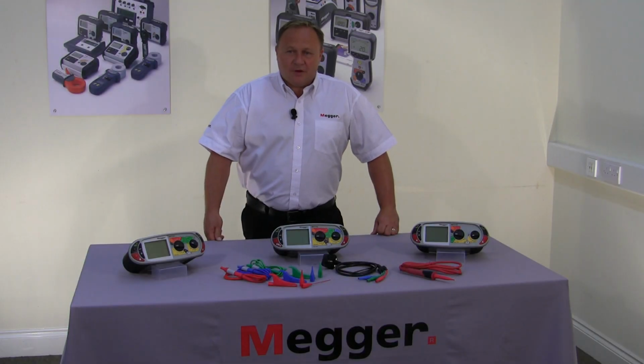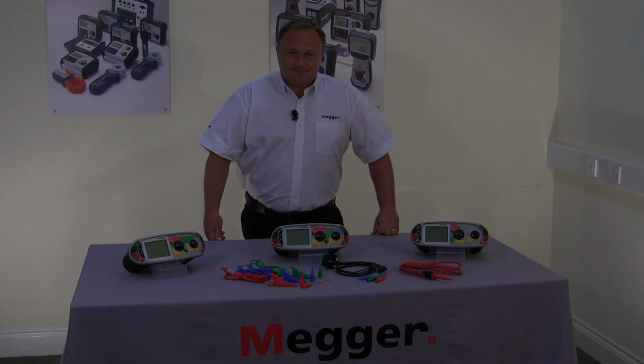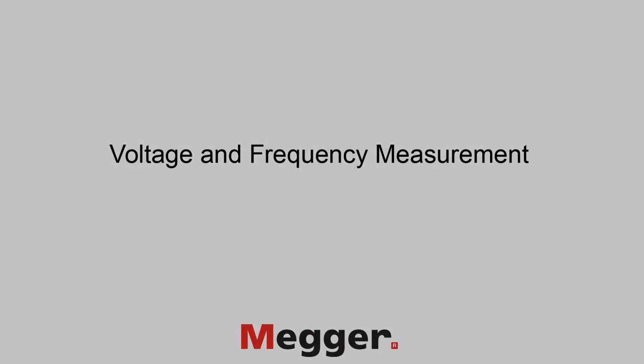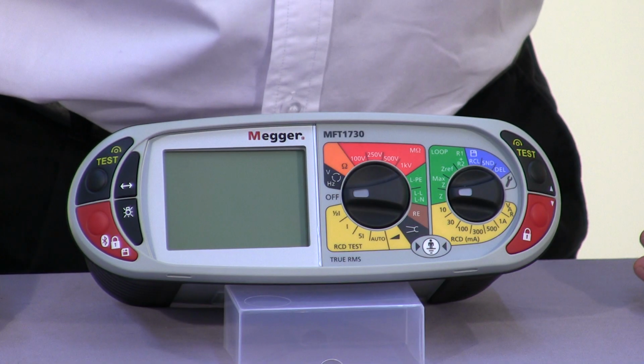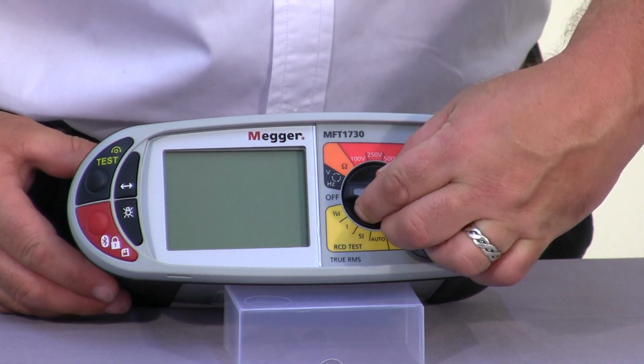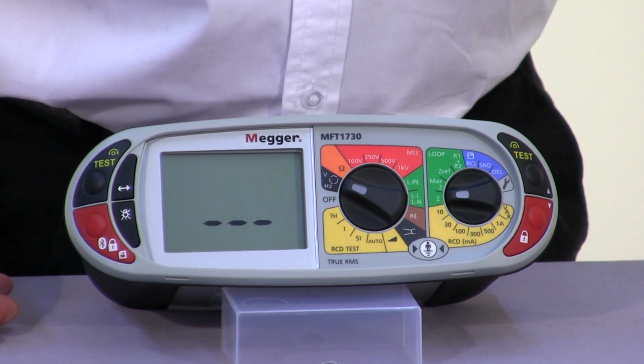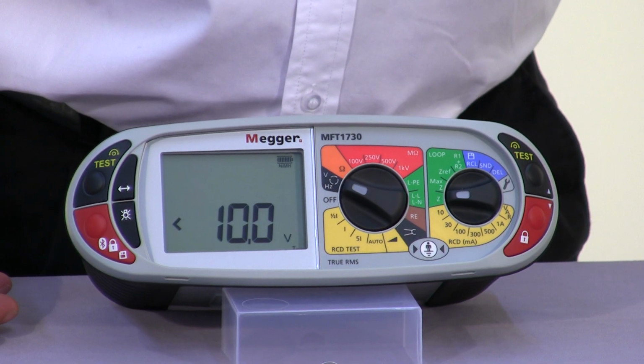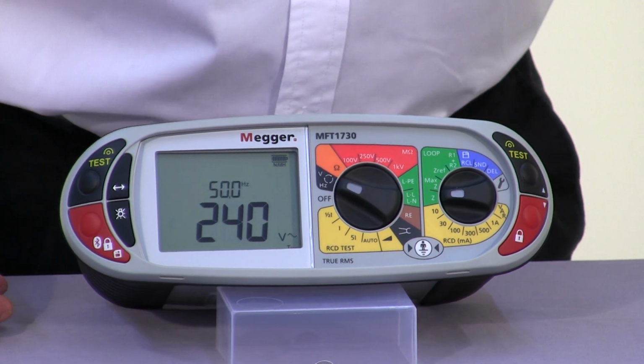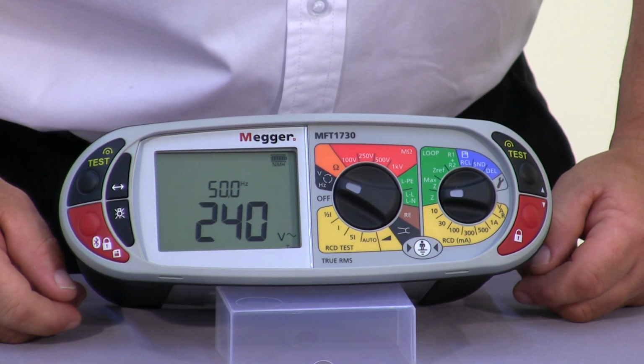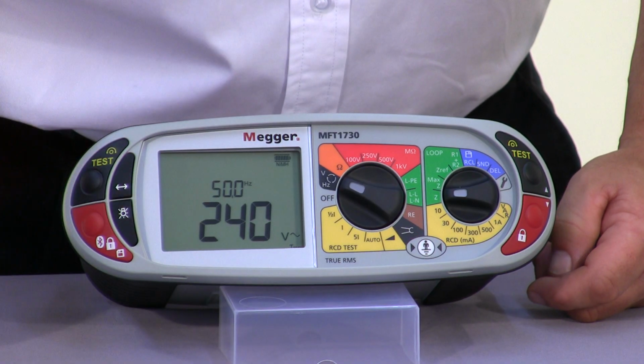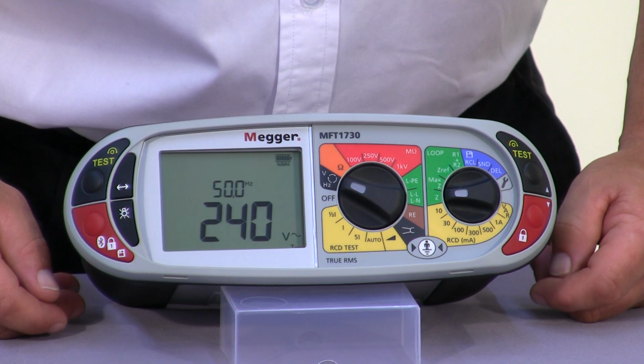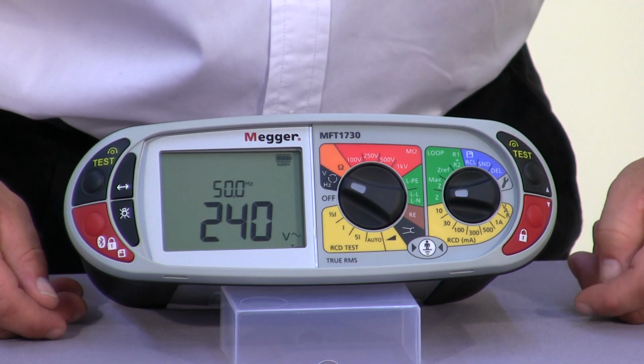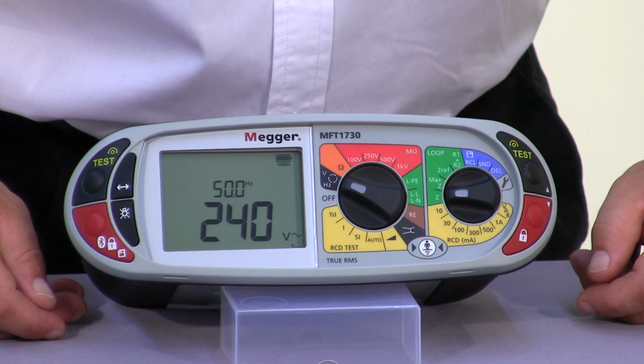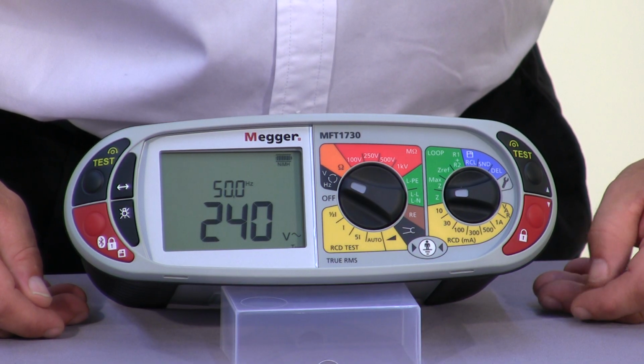What we'll do now is we'll run through a full product demonstration using the MFT1730. So, looking at voltage and frequency measurement, using the range selection knob, we go on to our voltage frequency, and just using a two-wire mains connection, you'll see on the display we're running at 240 volts, and the second parameter is indicating 50 hertz. Now, for phase rotation, we would use all three wires, and the indication on the screen would confirm the actual phase rotation for you.